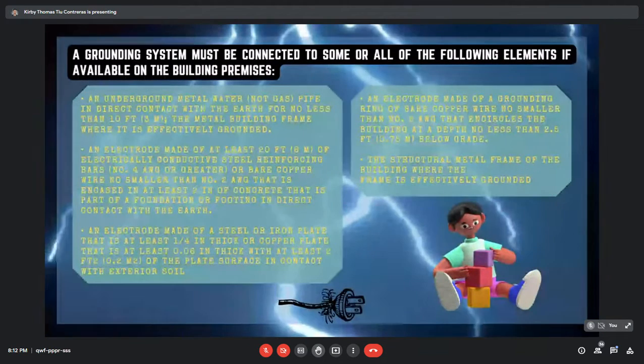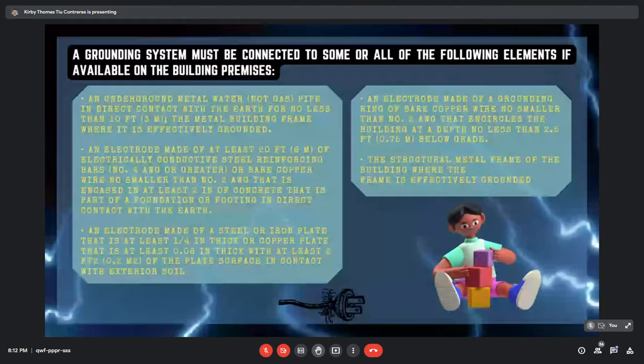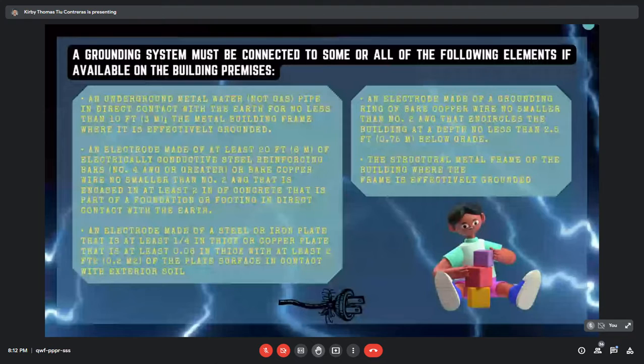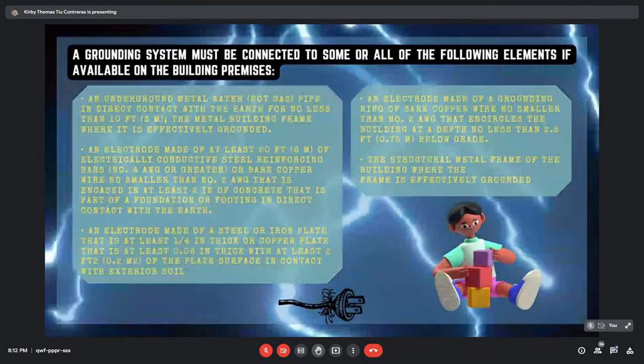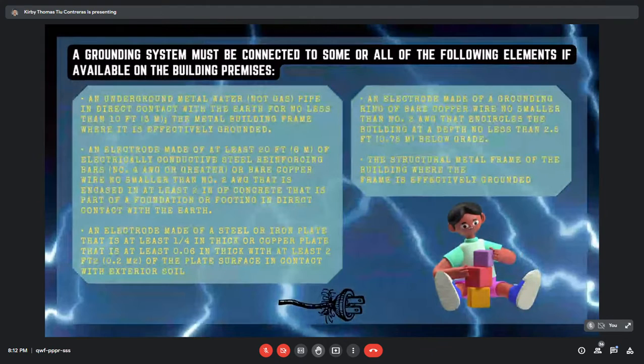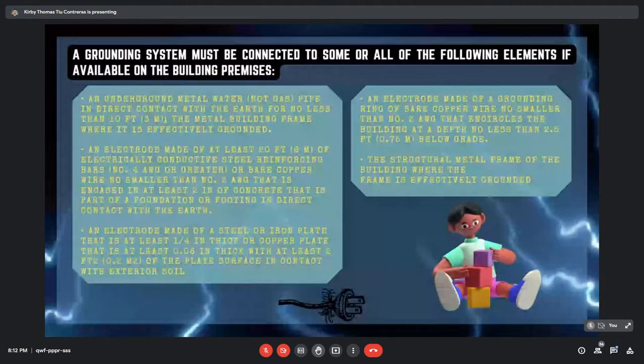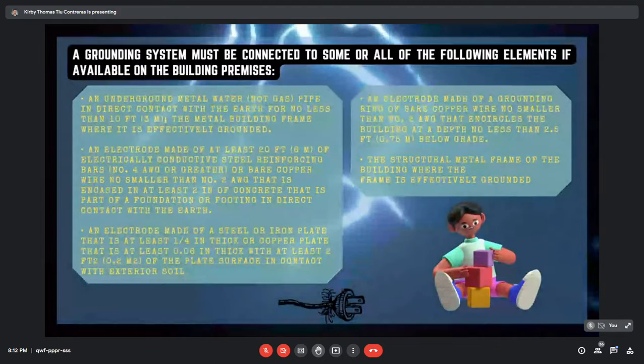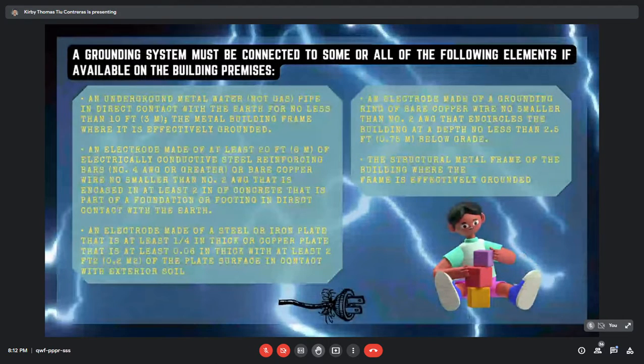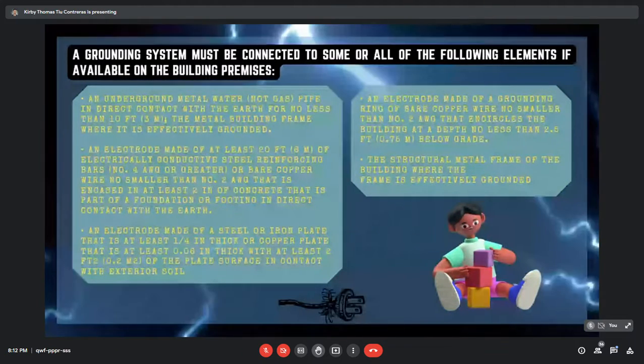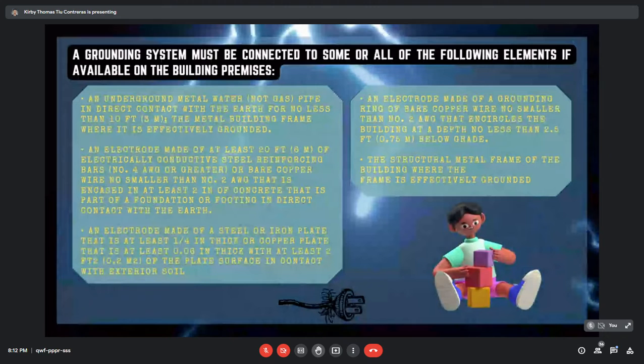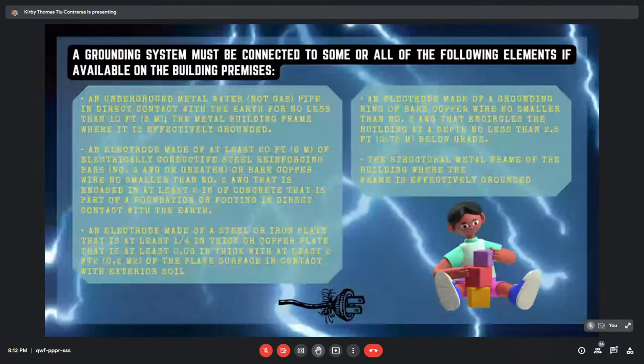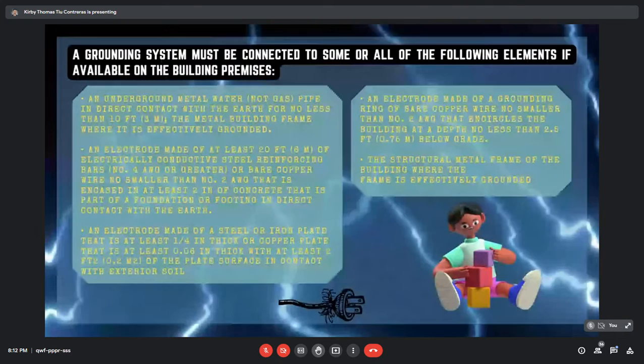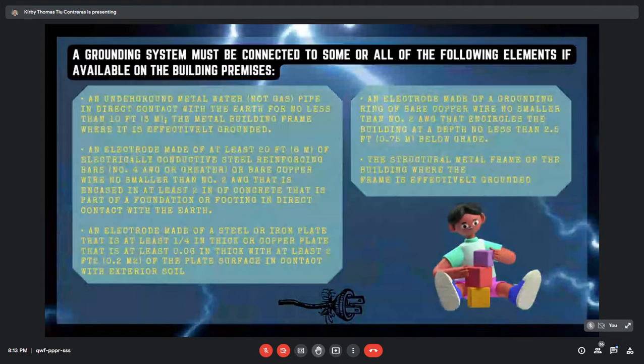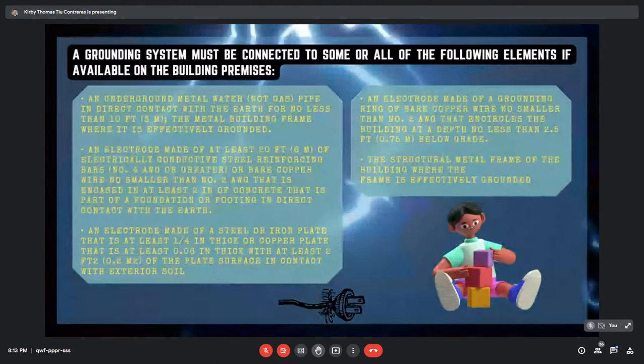And we have a grounding system that must be connected to some or all of the following elements if available on the building premises. An underground metal water pipe in direct contact with the earth for no less than 10 feet. The metal building frame where it is effectively grounded. An electrode made of at least 20 feet of electrically conductive steel reinforcing bars or bare copper wire no smaller than number 2 AWG, encased in at least 2 inches of concrete that is part of the foundation or footing in direct contact with the earth.